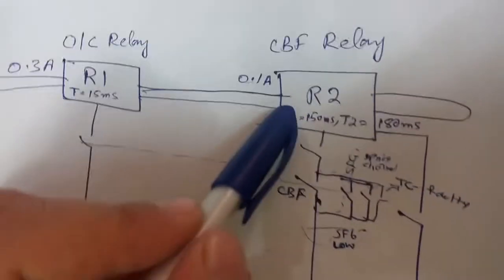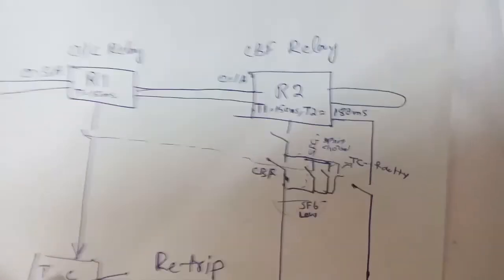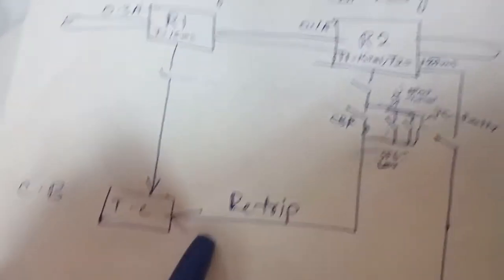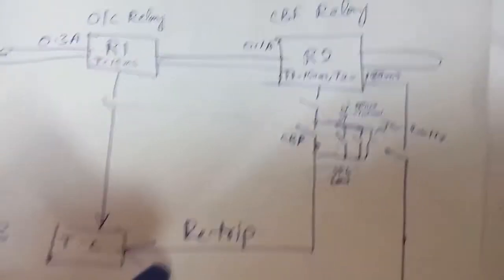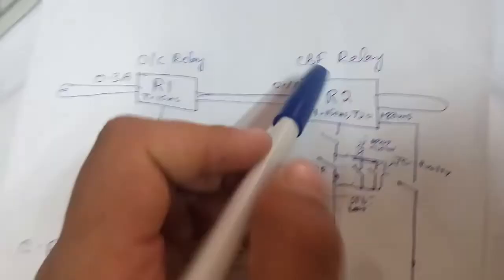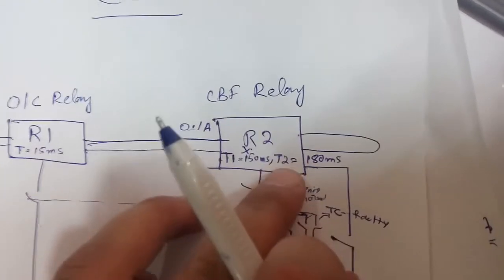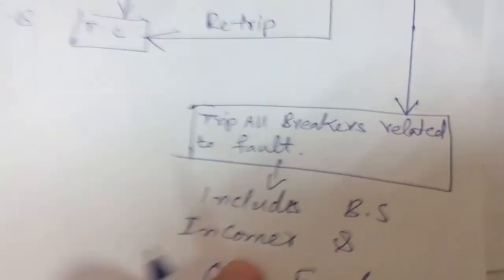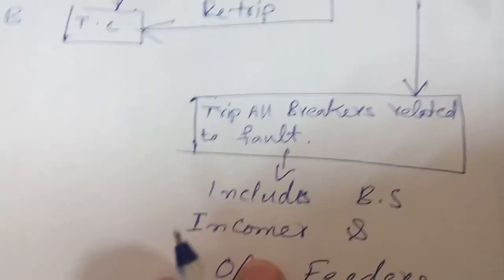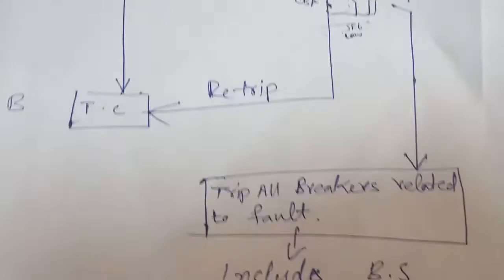Another concept: instead of using T1 and T2, some schemes do not give the same breaker a re-trip chance, because the breaker has already failed. In those schemes, we keep only one timer, and after that time is reached, it trips all related fault-side breakers directly. This completes the whole concept of circuit breaker failure. Now we move to the setting and configuration.